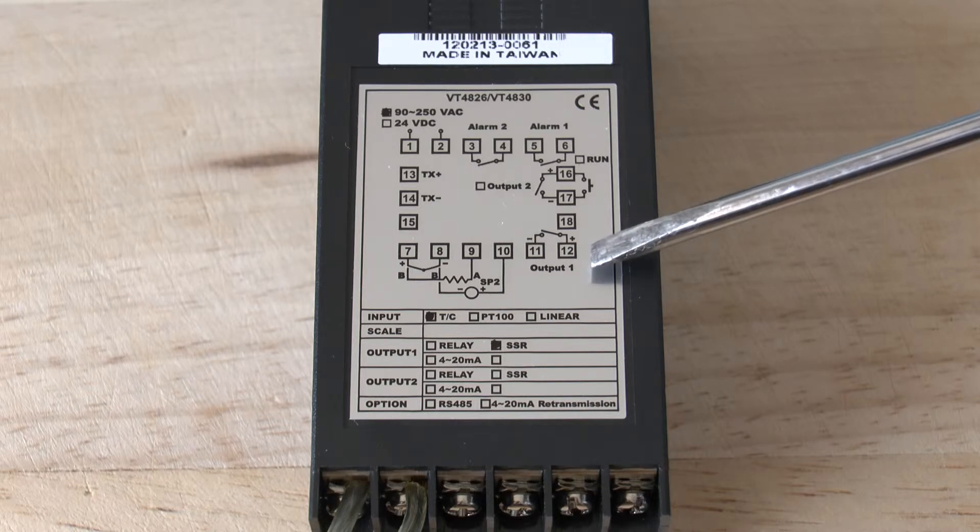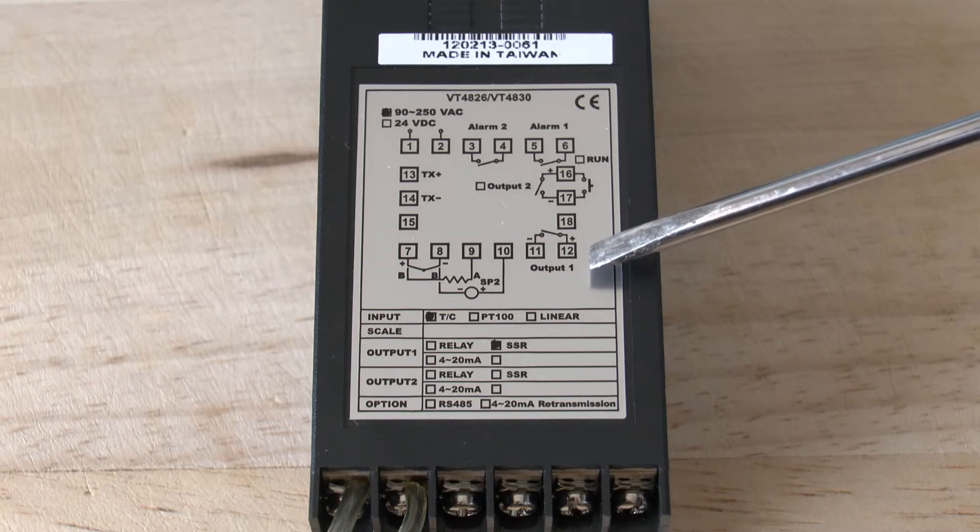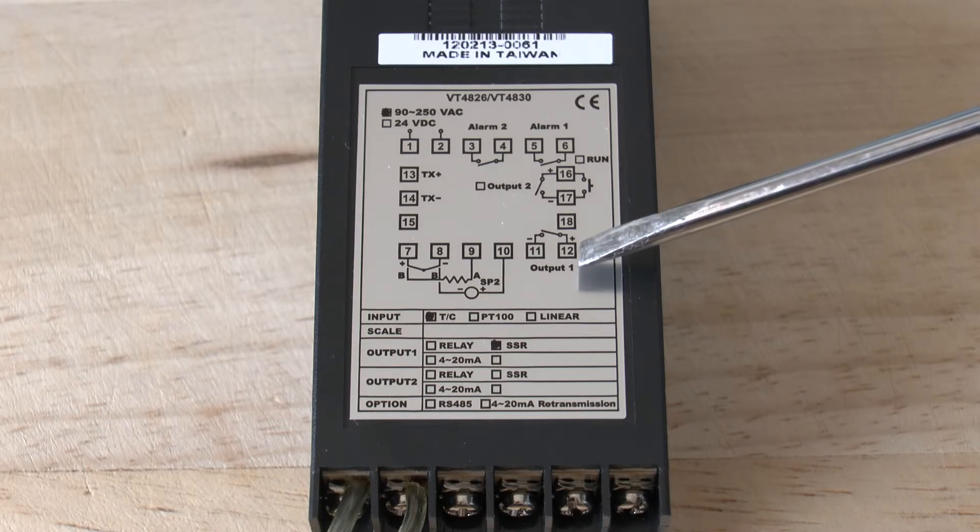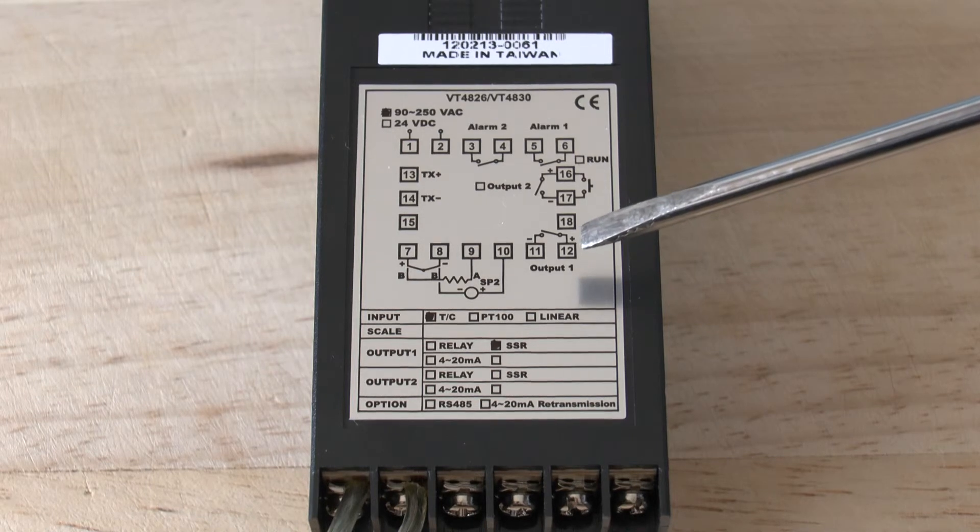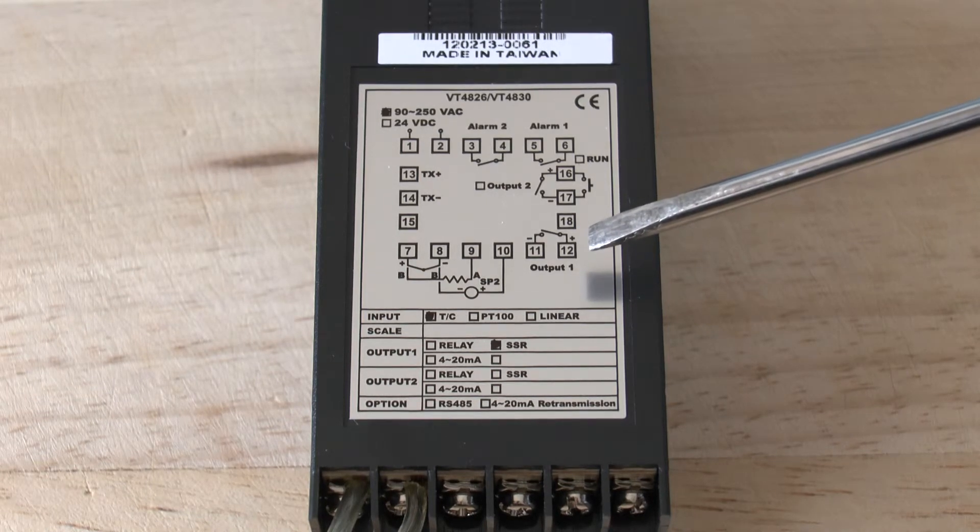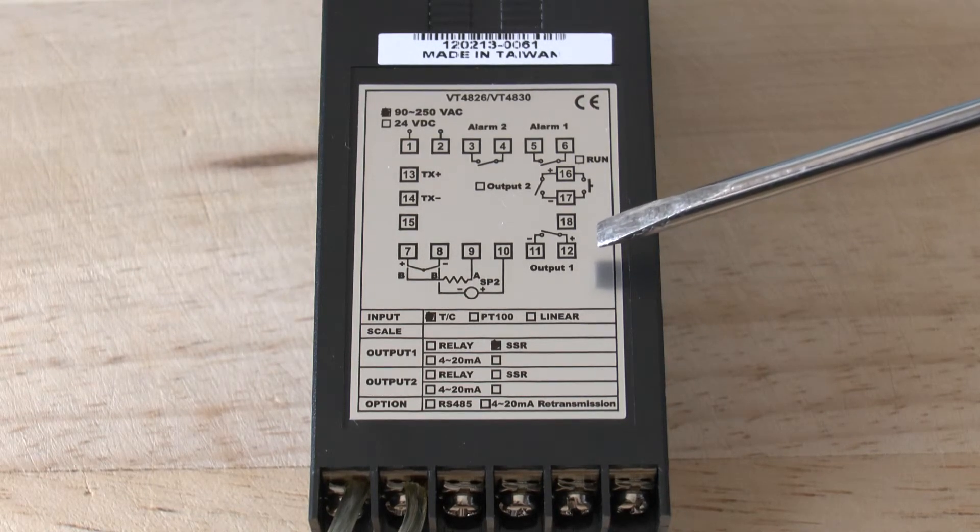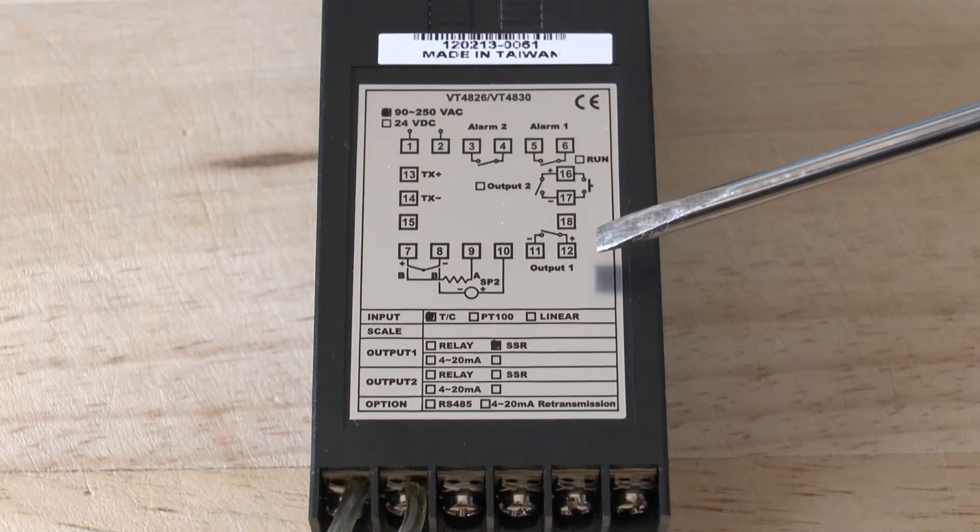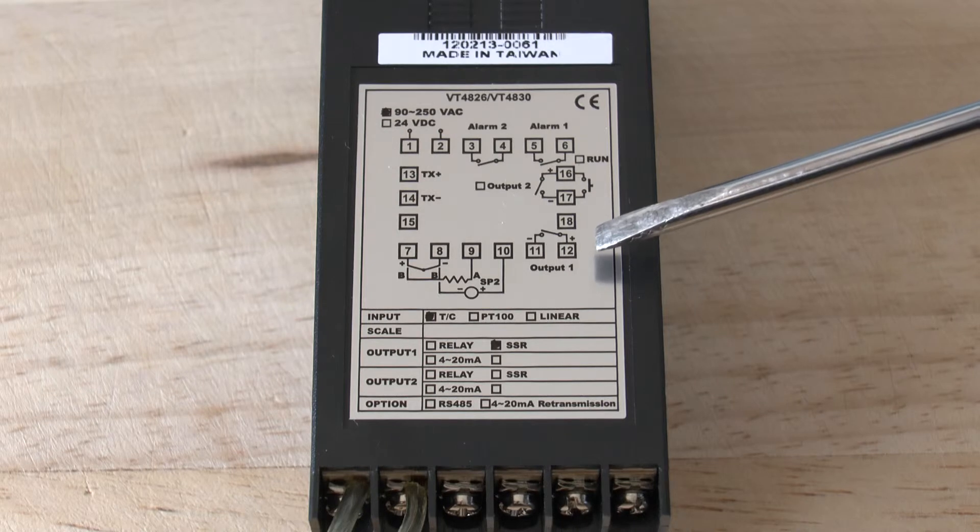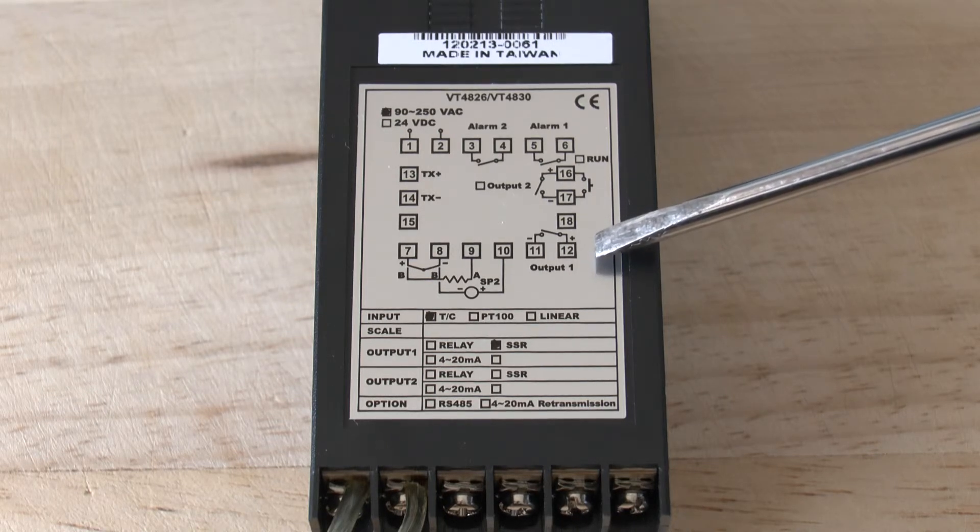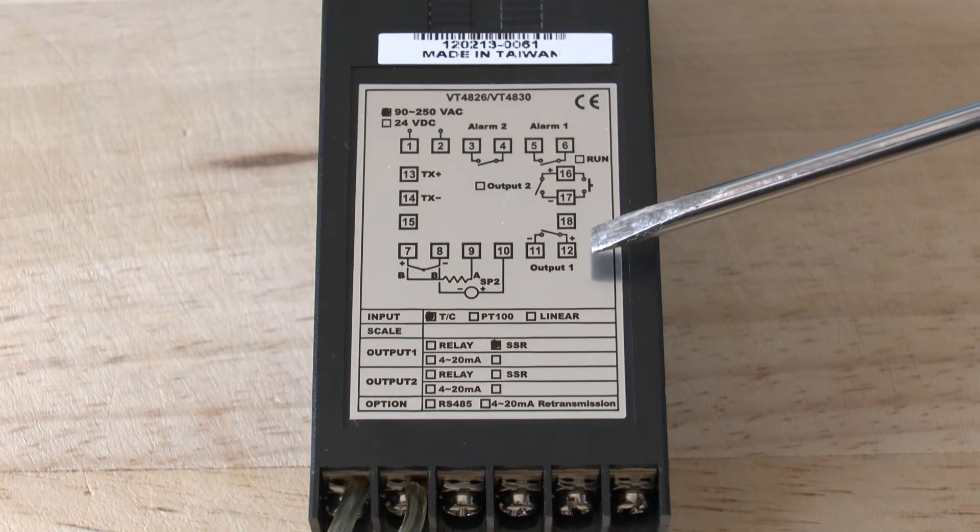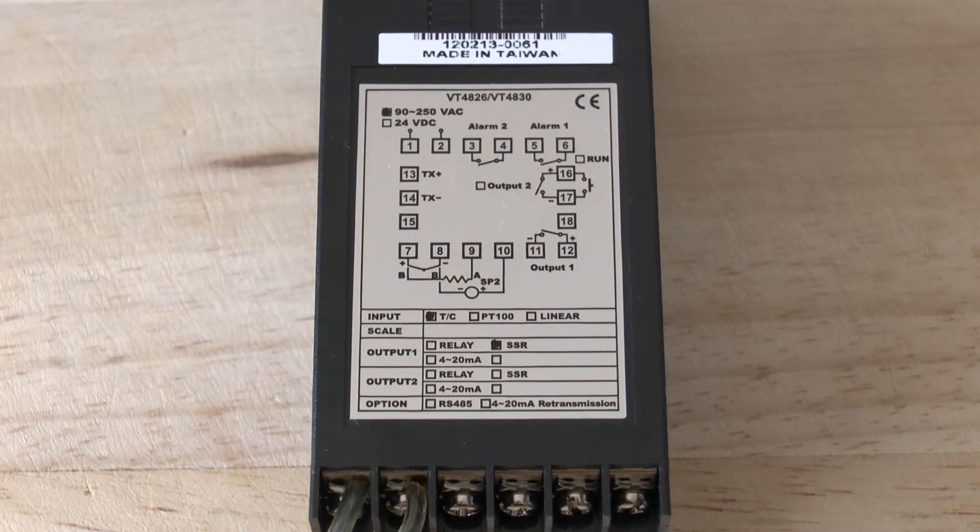In the solid state relay configuration, terminal 12 is the positive terminal and terminal 11 is the negative terminal. The output may also be an analog output, such as a 0-10 volt or a 4-20 milliamp, and then again, terminal 12 will be the positive terminal of the loop and terminal 11 the negative terminal of the loop.